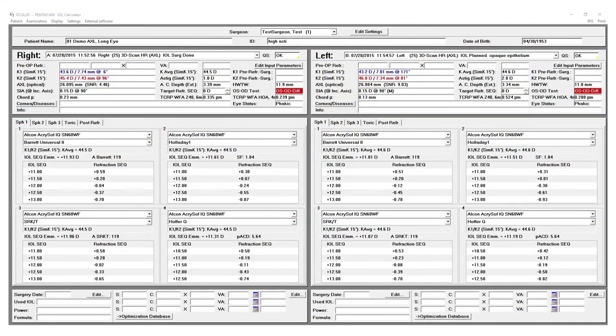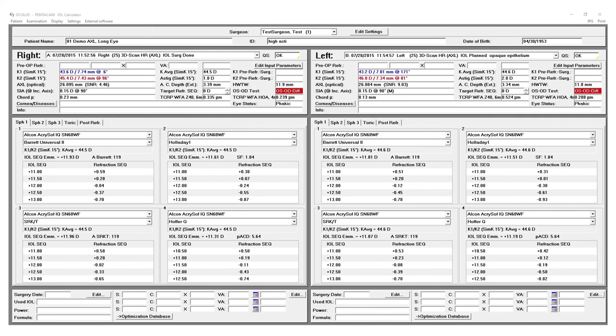With the Pentacam AXL we've added not only the axial length but we do have our IOL calculator built in as well. The IOL calculator is good for any type of eye whether it's a normal cornea, post-refractive, or for corneas with astigmatism where you would like to implant a toric. For normal corneas we have the Holladay One formula, SRKT formula, the Hoffer Q formula, and the Haigis formula.